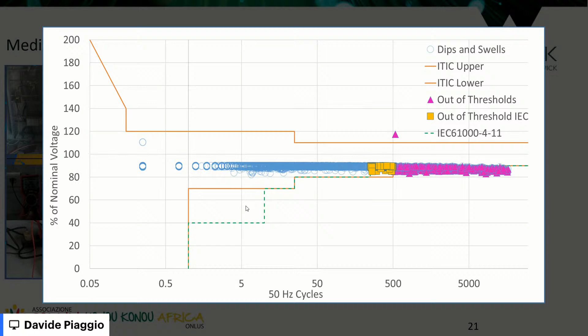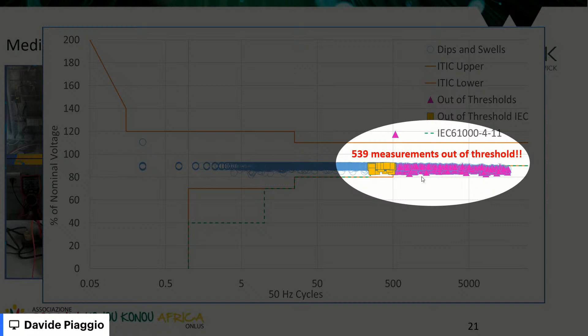And what we found, referring to these two curves that come out of the standards, is this: the green one is for medical devices and gives us only a lower threshold, while the orange one is for IT equipment like computers. But we all agree that nowadays medical devices are more and more advanced and looking like IT equipment. Potentially we had over 500 measurements out of threshold. So this could be one of the reasons why many devices that arrive functional with a donation get broken quite easily. And then they get abandoned because there are no spare parts to fix them, or maybe there is no expertise available in the hospital to fix them.